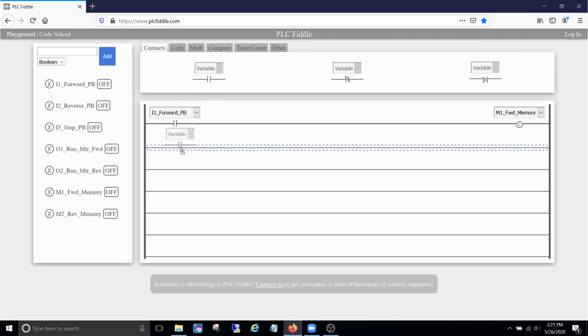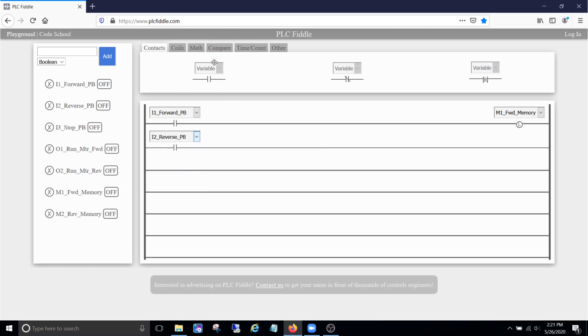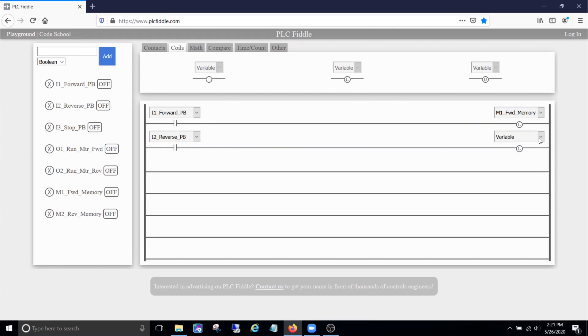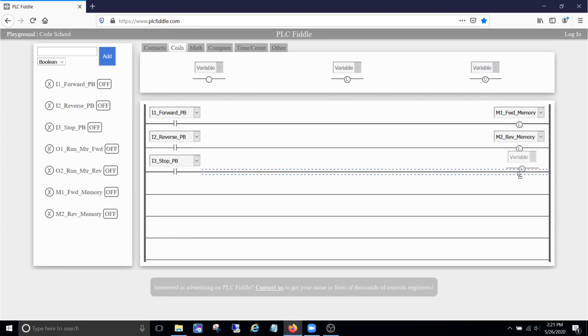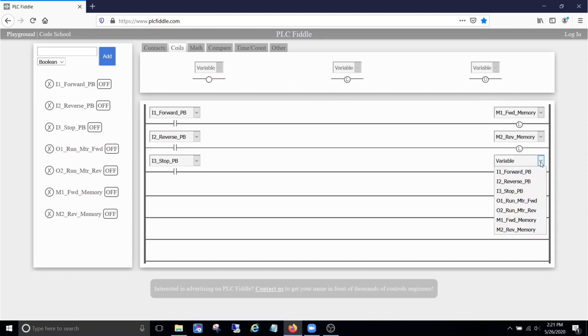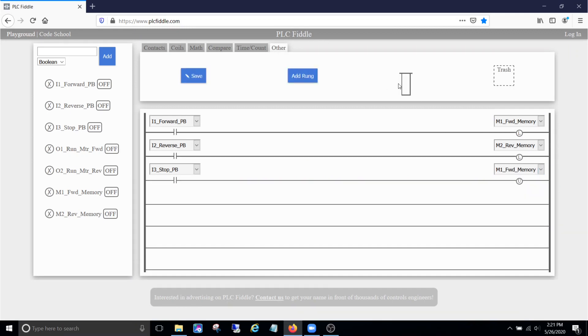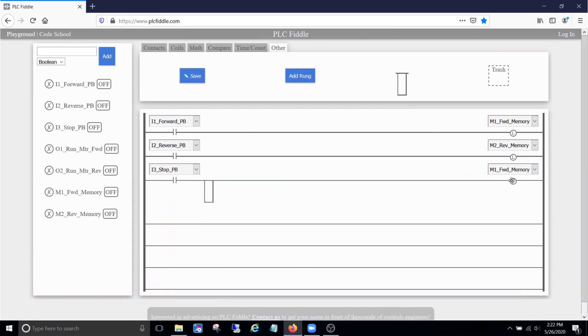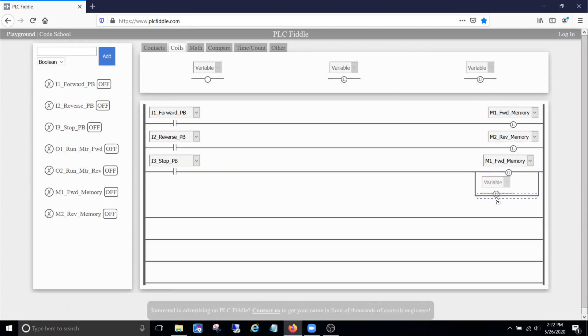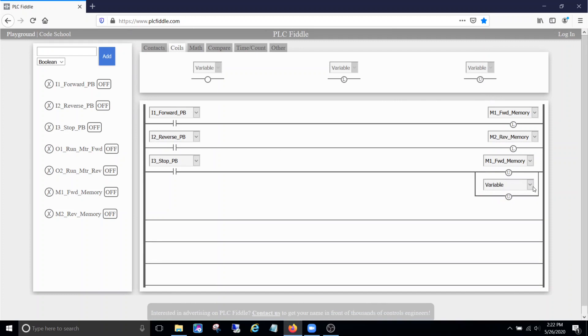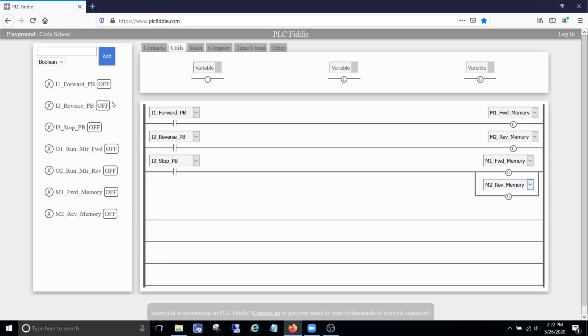We press the reverse button, we cut the reverse memory on. And then we'll have the stop button stop both of them. So we're just going to drop a little branch down here on this rung. We'll move this unlatch inside there just like that. Alright, so right there, the forward button cuts on the forward memory. Down here the stop button will unlatch it. The reverse button will latch the reverse memory, and that stop button will unlatch it. So let's walk through that right quick. Let's test it.